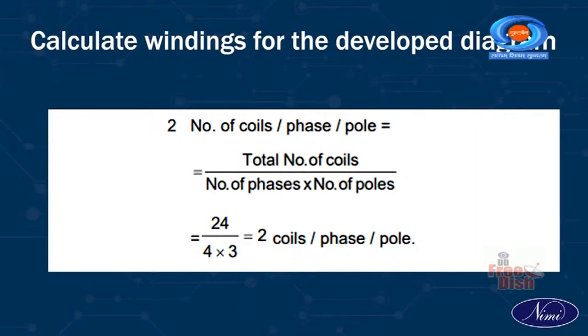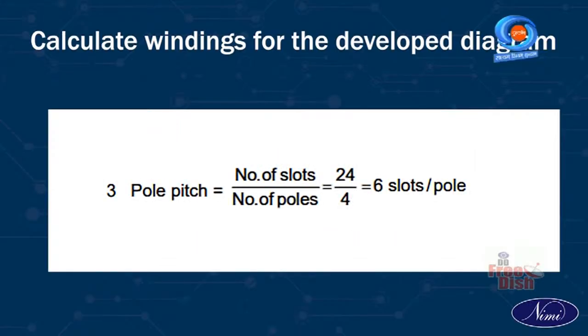2. Number of coils per phase per pole equals total number of coils divided by total number of phases into number of poles equals 24 divided by 4 into 3 equals 2 coils per phase per pole. 3. Pole pitch equals number of slots divided by number of poles equals 24 divided by 4 equals 6 slots per pole.